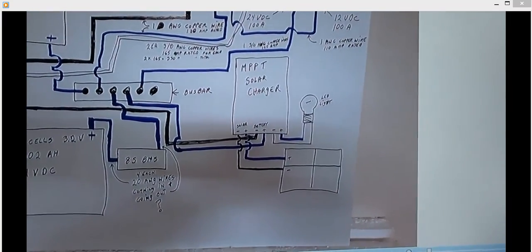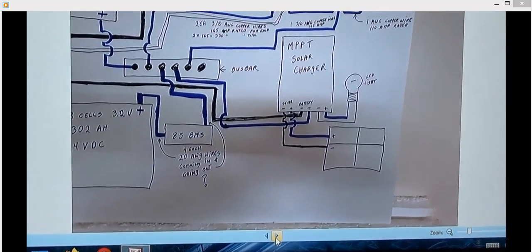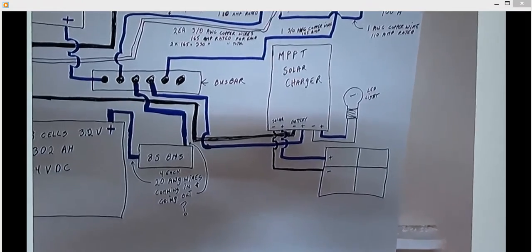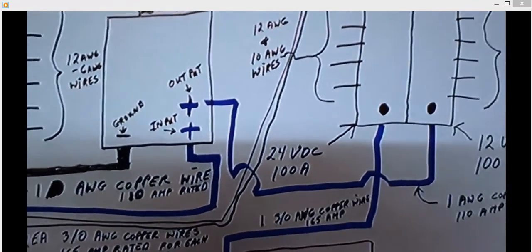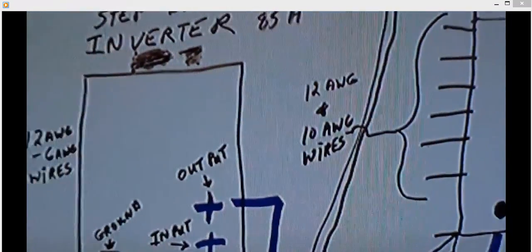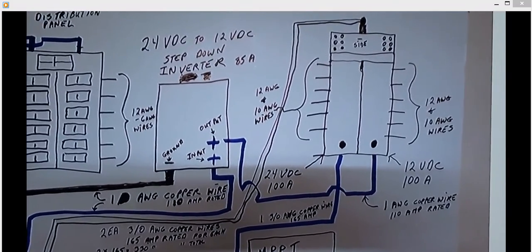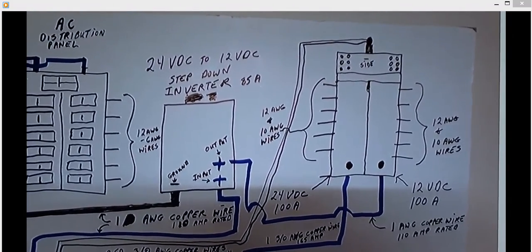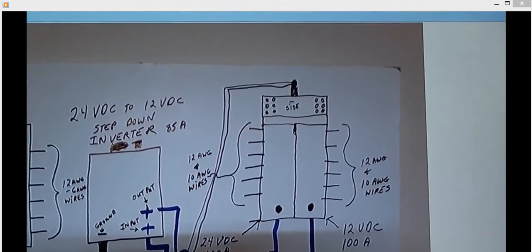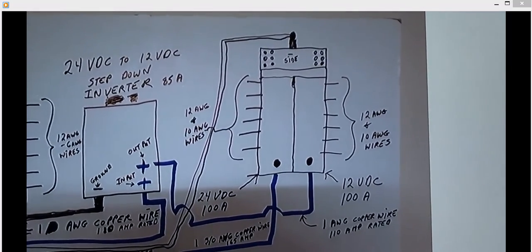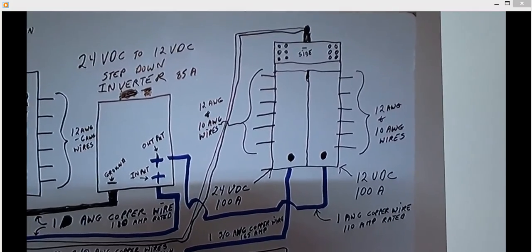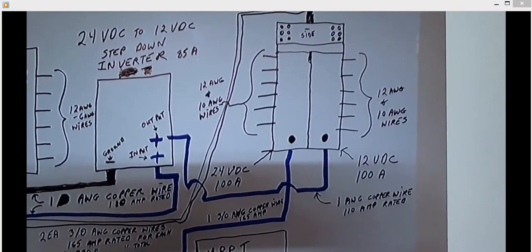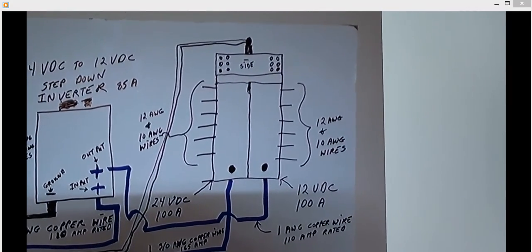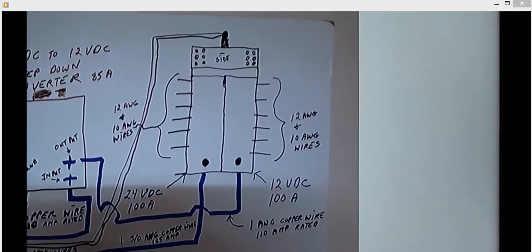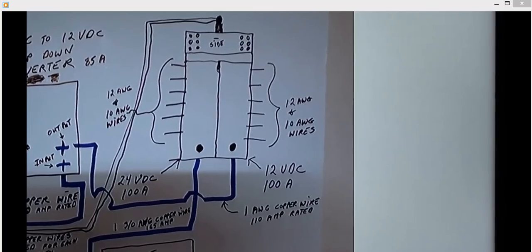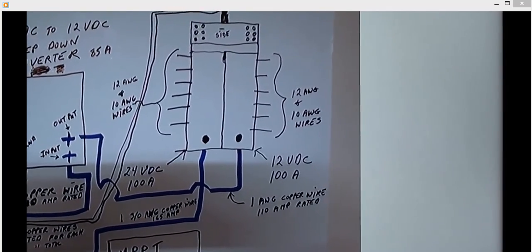And you got the MPPT solar charger with the solar panels and the hookups, and I got a 24 volt DC to 12 volt DC step down inverter, 85 amps. And then I got a 2-way fuse box, so the right side could be 12 volts DC, 100 amps, and the left side can be 24 volts DC, 100 amps coming straight off the bus bar. The 12 volt DC side will only get 85 amps because that's the size of the inverter. Then one AWG copper wire rated at 110 amps.